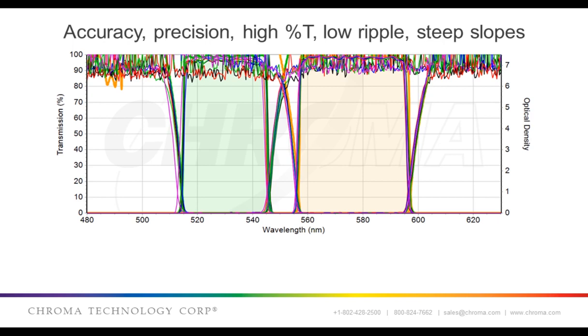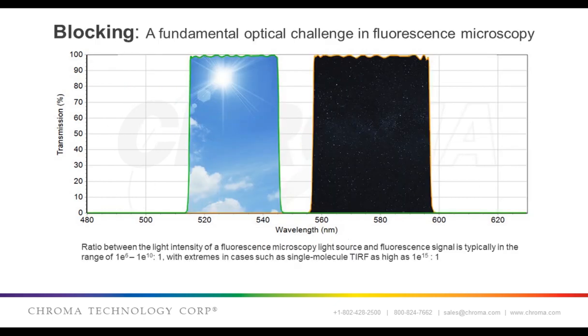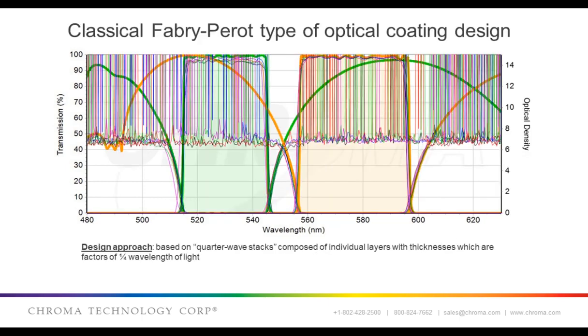What's not obvious here is why this blocking is necessary. The difference in brightness between the excitation light incident on the sample and the emitted fluorescence is similar to the difference between the lux from the noonday sun in early summer and a dark, moonless, starry sky. This difference can cover a wide range, but it's often a million to a billion fold and can be much greater. So optical density is extremely important in many fluorescence applications.